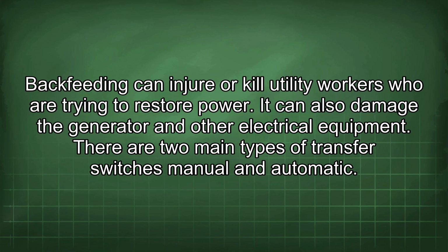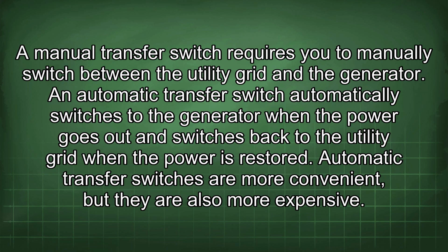There are two main types of transfer switches: manual and automatic. A manual transfer switch requires you to manually switch between the utility grid and the generator. An automatic transfer switch automatically switches to the generator when the power goes out and switches back to the utility grid when the power is restored. Automatic transfer switches are more convenient, but they are also more expensive.